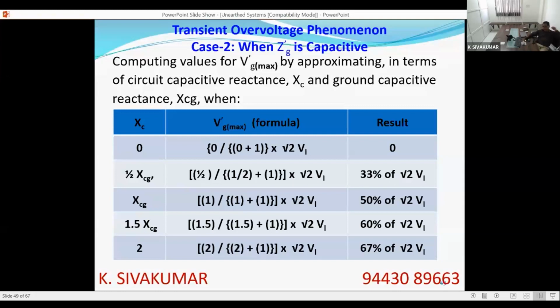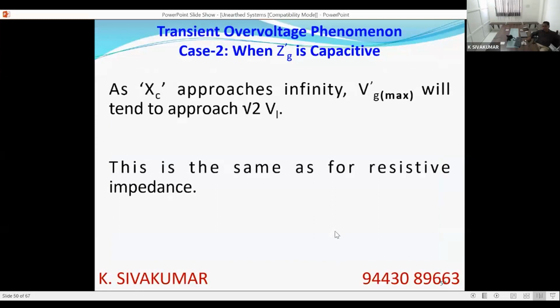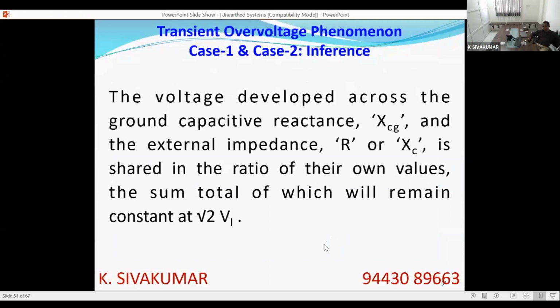So if you keep on giving values, if the XC approaches infinity, the maximum value will be root 2 VL. Because as this goes on increasing, this becomes negligible, almost 0, so the ratio becomes 1 into root 2 VL. The maximum value it can reach is root 2 VL only. Here also, like in resistive impedance, as XC approaches infinity, the maximum voltage the load or the network will see during fault is root 2 VL only. That is also not to be worried about, because this system is designed for withstanding a peak voltage of root 2 VL. Now, the voltage developed across ground capacitance XCG and the external impedance R or XC is shared in the ratio of their own values, the sum total of which will remain constant at root 2 VL.